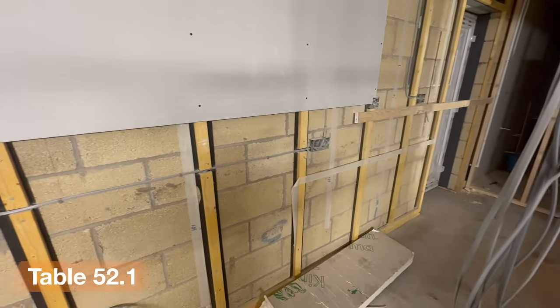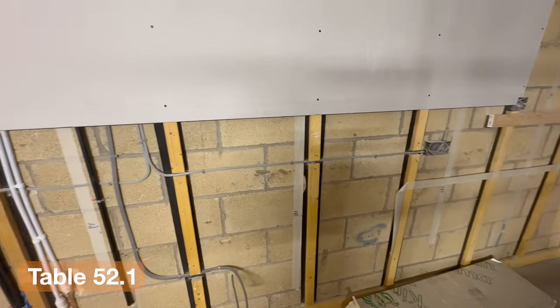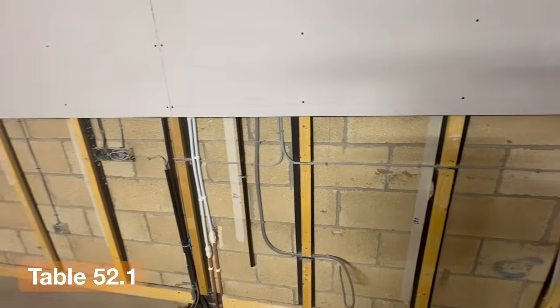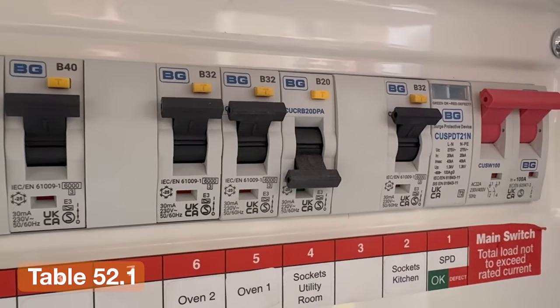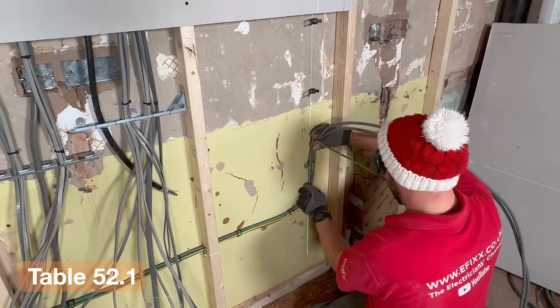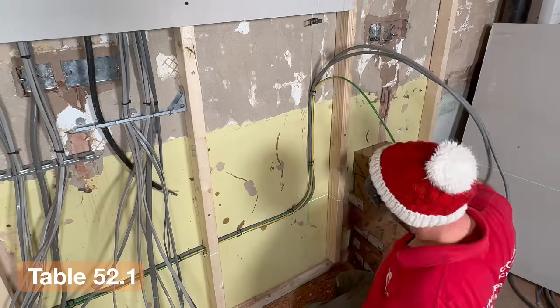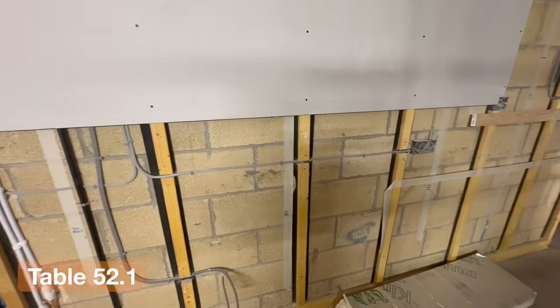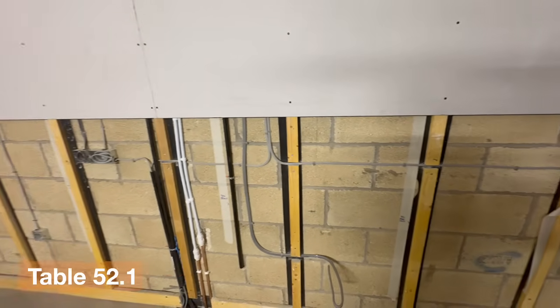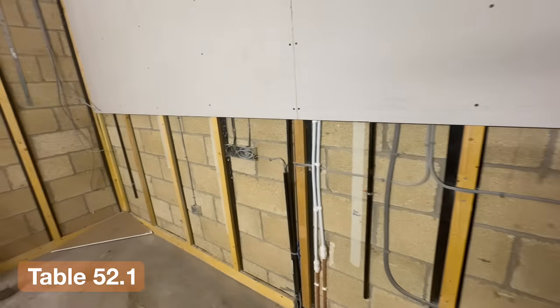For example, where a cable is installed at a depth of less than 50 millimeters, additional protection is typically required, usually by means of an RCD. But once you go deeper than 50 millimeters, those requirements can change depending on the wall construction. And if the wall contains metallic parts, that also affects what is required. So this is no longer just about putting cable in a safe zone, it is about understanding the construction of the building and installing the cable accordingly. That same thinking carries through when you move outside.